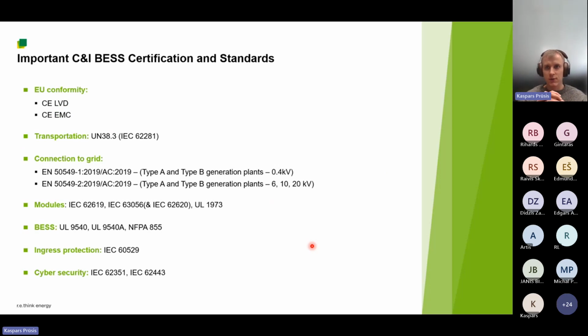Also, one slide regarding certifications and standards that are required. So all these solutions must conform with European Commission regulations, EU CE certification, and of course the EU EMC directive. Also, they have to comply with the EU transportation directive, which is UN 38.3. Connection to the grid we already discussed. For type A, it's 50549-1, and for type B power plants, it's 50549-2. For battery modules, there are some standards that are relevant, but they are not mandatory. So those are listed here as well.